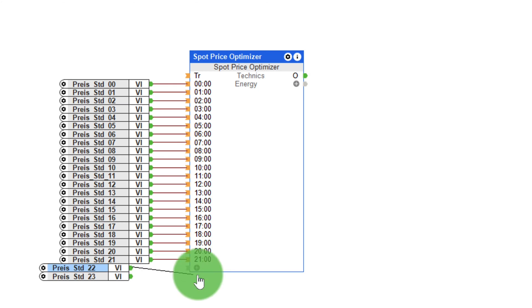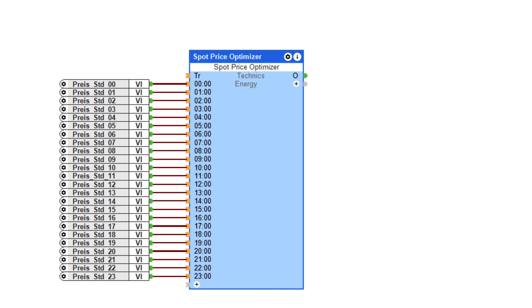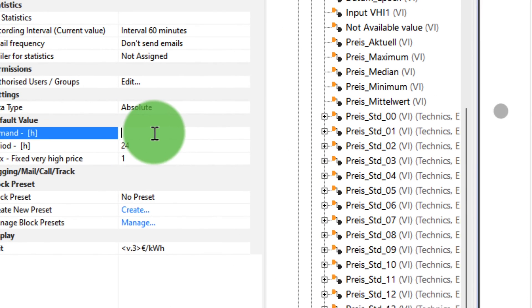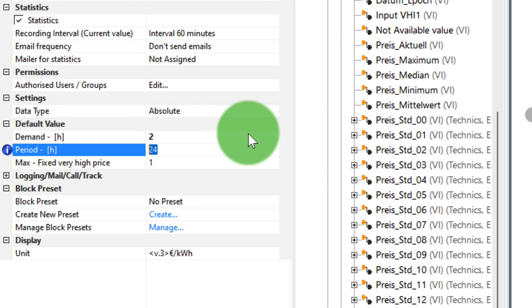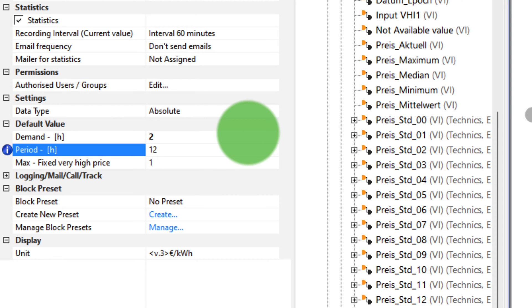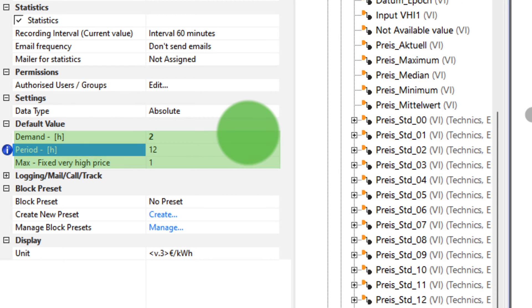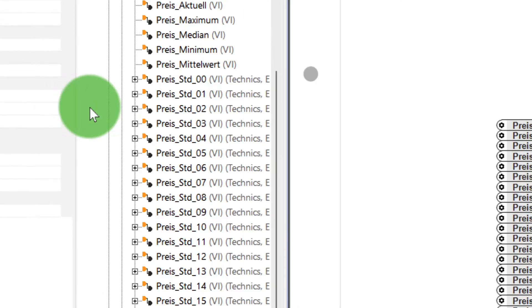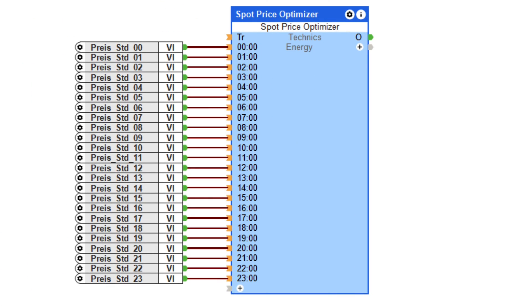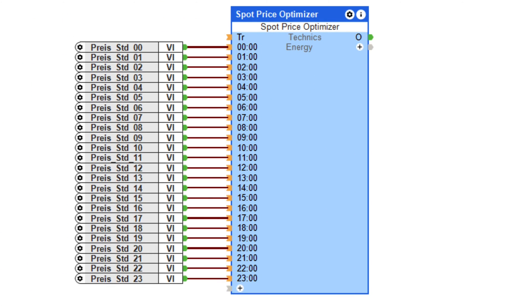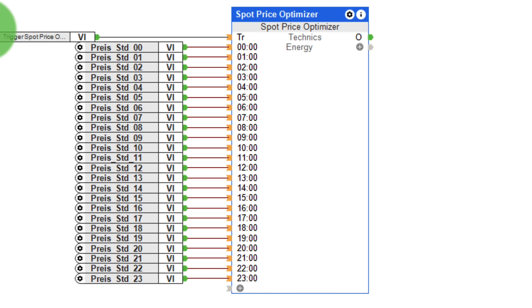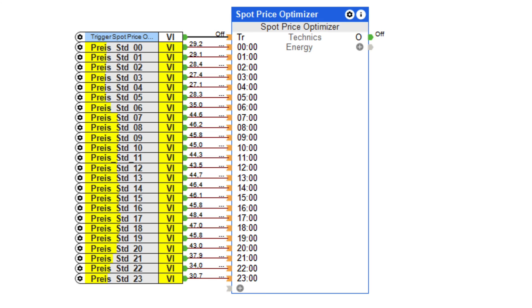The new function block offers two options. On the one hand, consumers can be activated automatically exactly in those hours when the electricity price is lowest. To do this, first define the two parameters, period and demand, within the function block. Period is the period in which the cheapest electricity prices are to be determined, and demand corresponds to the activation period in hours. If the trigger input of the function block is now activated, it activates the output — in this example — for the two cheapest hours within the next 12 hours.